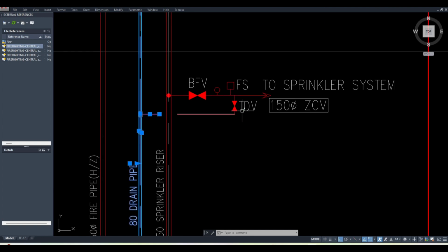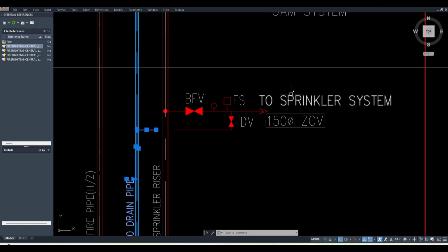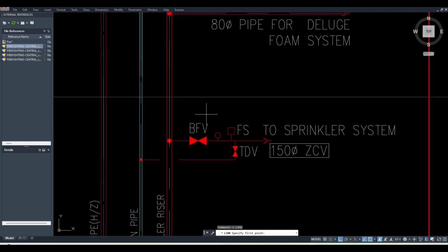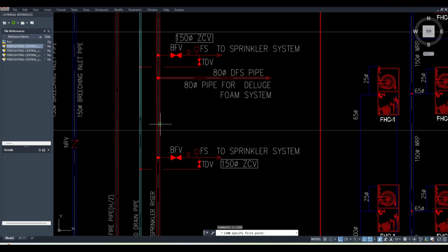and then it goes back. Now, from the installation point of view, what is important for you? The pipe, when you are taking from the zone control, if anytime you want to drain the water of the sprinkler system line, you always need to model that like this. If the pipe is going up and up and up, then whenever you need to drain this water, it can come back like this, like this, and like this. And from here, suppose you have the drain valve here, from here it can go like this, and then you can connect it here.